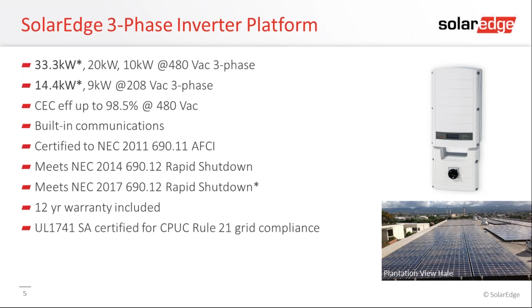12-year standard warranty on this inverter. You can expand it to 20 years. And then also another hot topic in the US right now is smart inverters. Basically, it's a new test standard called UL 1741 SA, and it gives our inverter the ability to do reactive power control, low voltage ride through, frequency ride through, anything that you would want an inverter to do to help support grid stability. Our inverters can do that. So right now we're in phase 1 of the rule, or phase 2 of the rule, where it basically says you just have to have an inverter that can do these things. And so all of our inverters do those things.